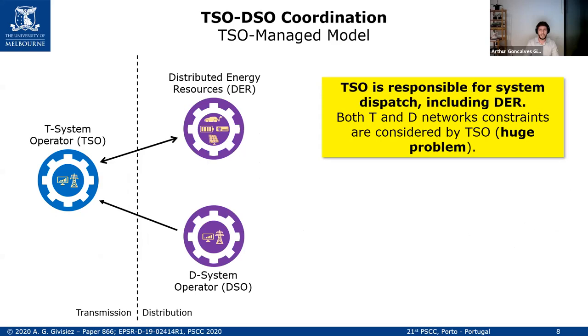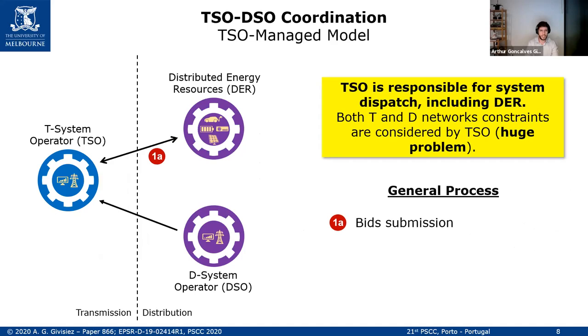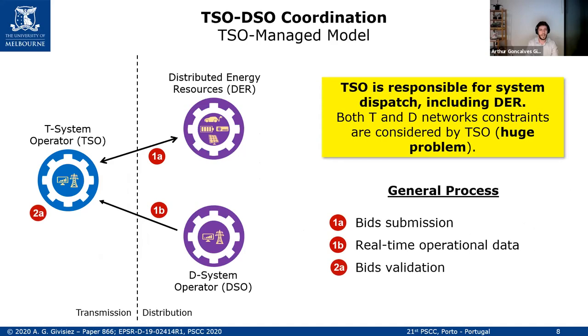Starting with the first model — the TSO Managed Model. The TSO is responsible for the system dispatch, including the DER, so both transmission and distribution network constraints are considered by the TSO. This is a large problem. The process starts with the DER submitting bids to the TSO. The DSO also sends real-time operational data to the TSO, so the TSO has the information to perform bid validation and dispatch, then sends the dispatch command to the DER.